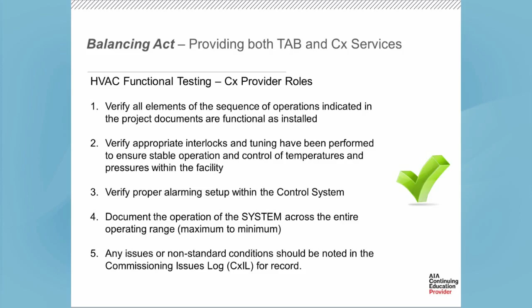And then really testing the operation of the system as a whole across the entire operating range, from maximum to minimum on the flow side, and then trying to replicate temperature control as well in a few different scenarios to really make sure that the loops are tuned in. And as you go through the seasons, even though you may be testing in only one season, you try to get a good feel of whether the system is going to continue to operate appropriately in the shoulder seasons and in the opposite seasons from when you're testing. And then obviously the commissioning provider is going to document any issues noted during the functional testing. It's not going to be recorded as a TAB issue. It'll be recorded as a commissioning issue.